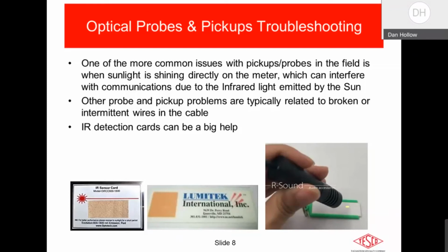And then I try another communication session and I hold that optical probe head over these little cards with the paper on them, and I see the flashing. Okay, great. Now I know that the infrared LED in my optical probe is working. I've got my software configured for the proper port. So now let's put it back on the meter and see if I can communicate with it.